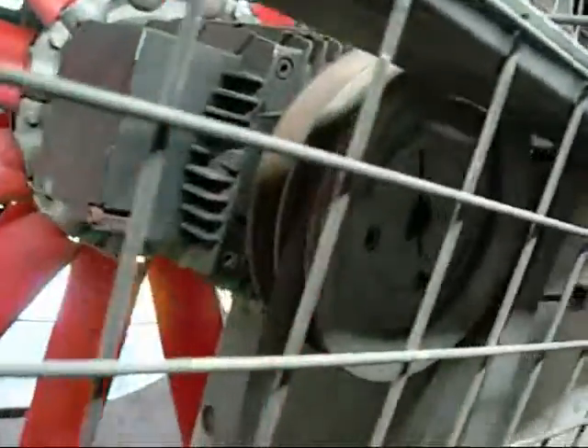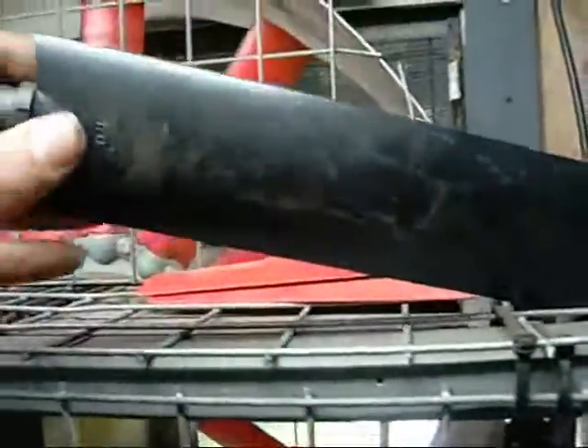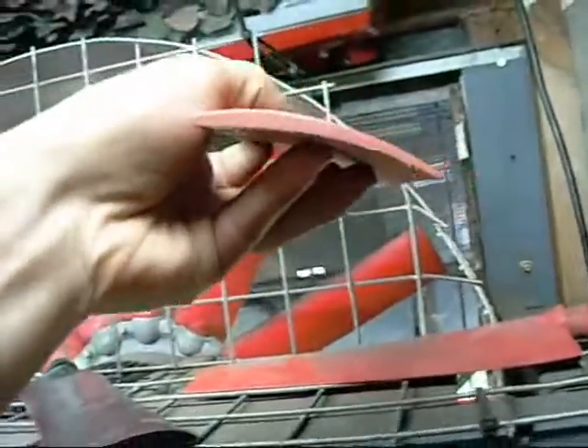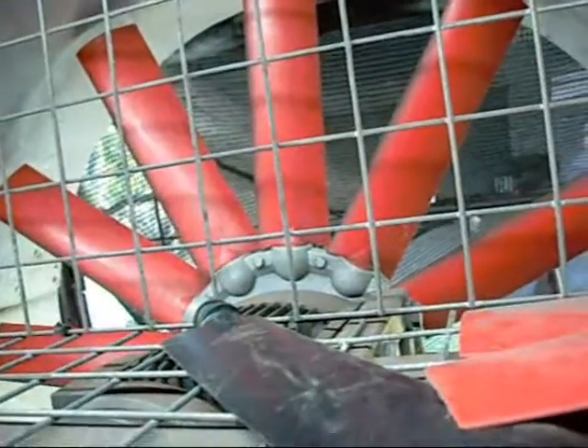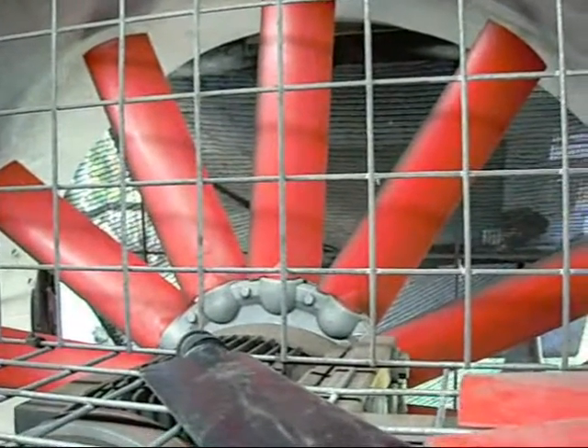There's a taper lock pulley, and there's my improvised bearing mount. These are some of the fan blades — this is the right hand glass-filled nylon, you can see the aerofoil design. Left hand polypropylene. Again, designed for a different type — if these were fitted to that drive plate they'd be pulling air into the room rather than discharging it. They're actually right hand blades configured to blow air rather than suck it.